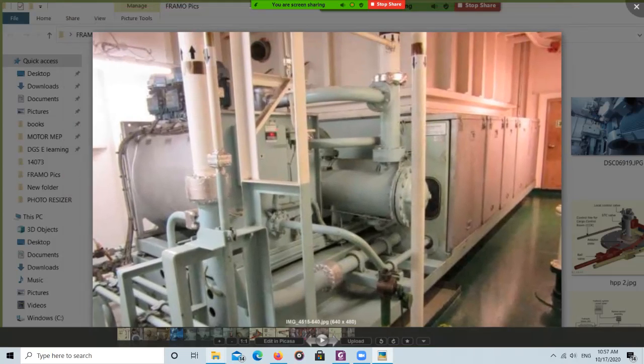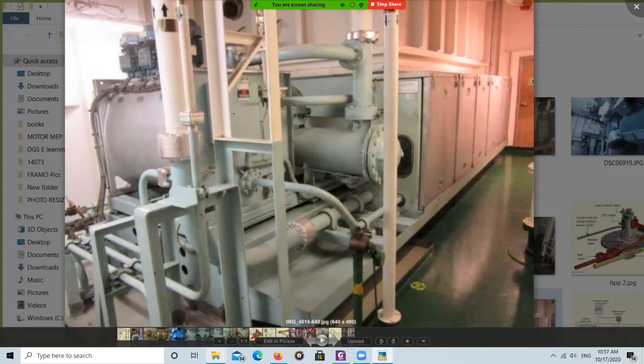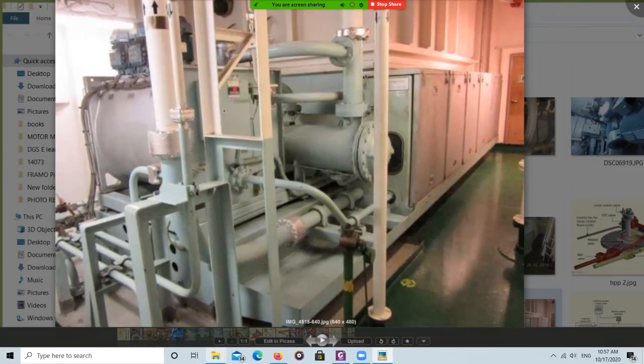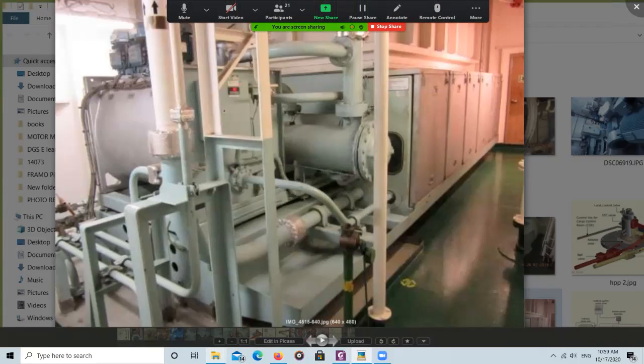There is one more pump to draw suction from a hydraulic oil storage tank — you can see the sounding pipe for this storage tank, located below this deck. Whenever the oil level inside the hydraulic tank drops below normal operating level, you take suction from that pump, attach a coupling to the system, and fill the hydraulic tank up to the required level. This storage tank is generally located outside the hydraulic room.